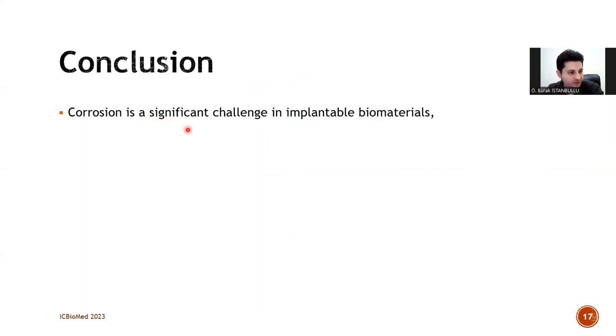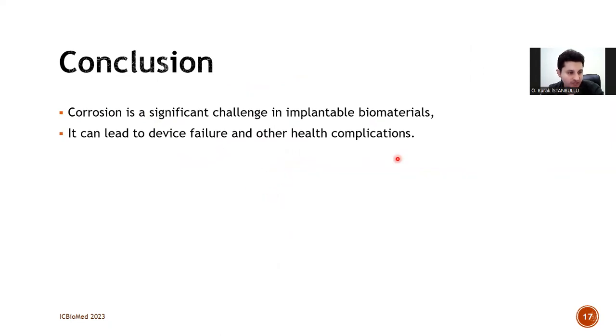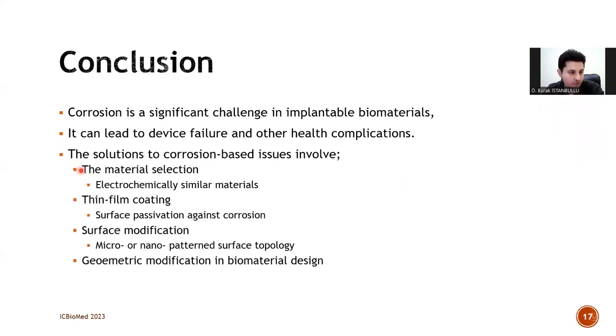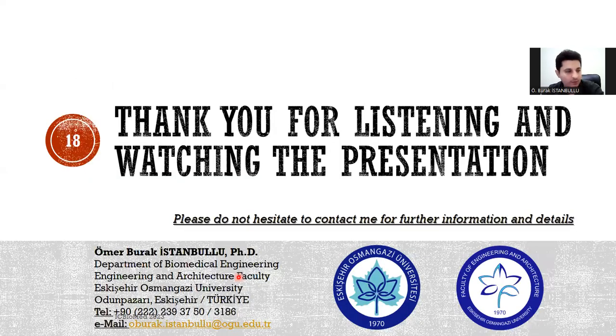To sum up, corrosion is a significant challenge in implantable biomaterials and may lead to device and material failure and other health complications such as biocompatibility issues. The solutions to corrosion-based issues involve material selection — selecting electrochemically similar materials — or applying thin-film coating on the material surface to passivate it against corrosion. We can also apply surface modifications such as micro or nanopattern surface topology, or geometric modification in the biomaterial design. Thank you for listening and watching this presentation; please do not hesitate to contact me for further information.